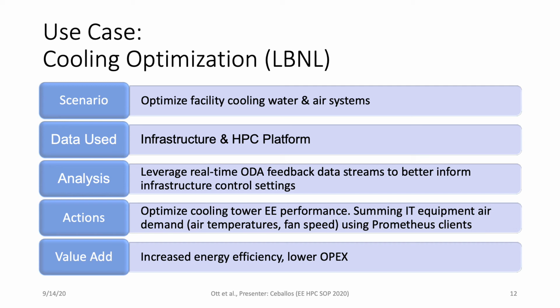This strategy promises to be more agile for energy performance than simply setting the infrastructure supply air rates based on a cubic foot per minute per kilowatt rule of thumb using the IT equipment power ratings.